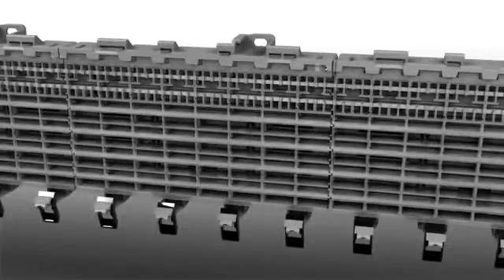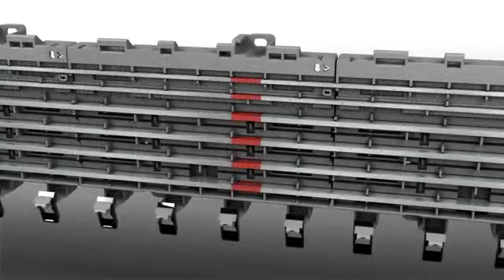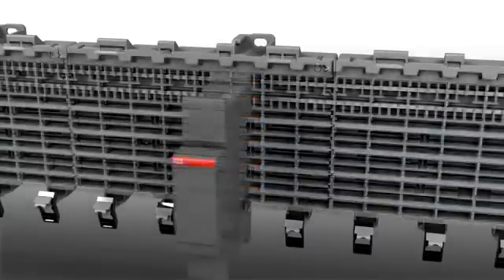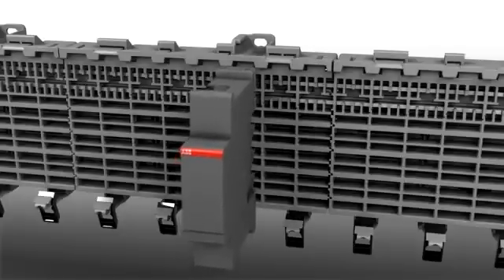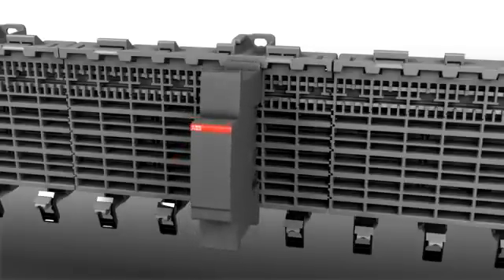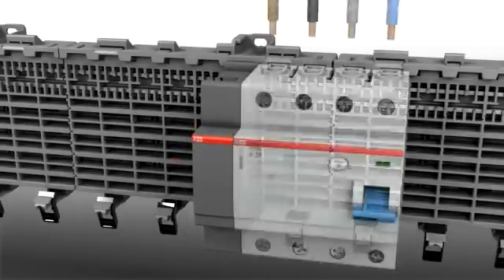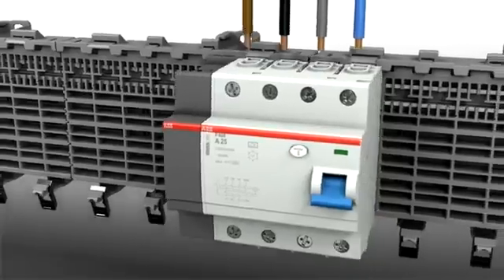Bus bars can be isolated. Using an isolator, this allows you to create different circuits on the sockets. By doing this, you can create groups that are protected against residual currents, for example. In such cases, power is supplied by a residual current circuit breaker.